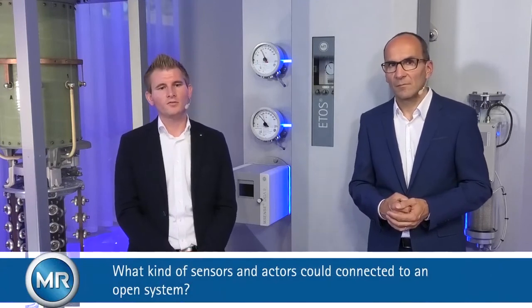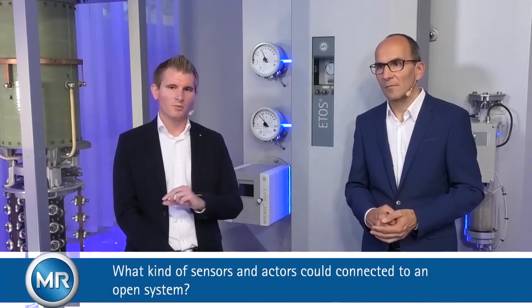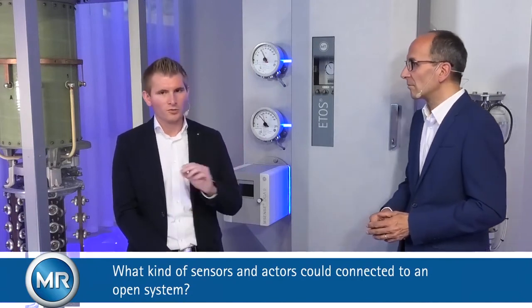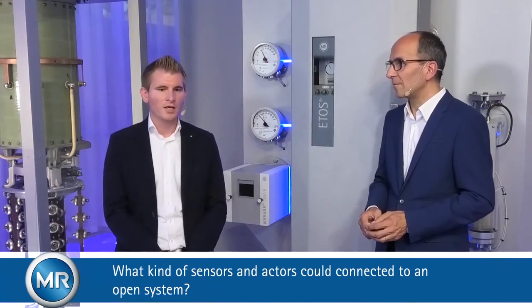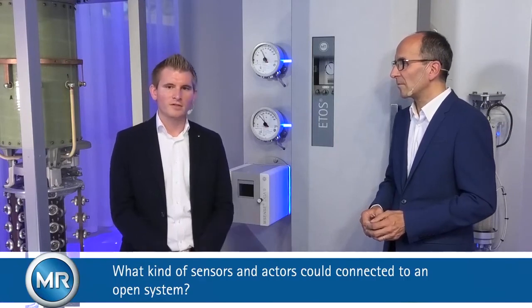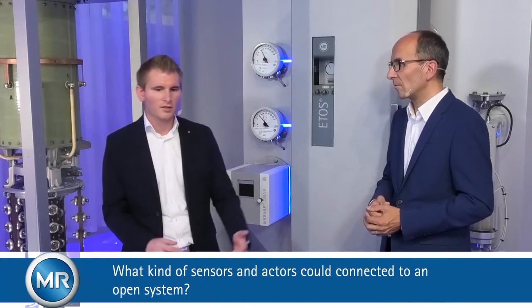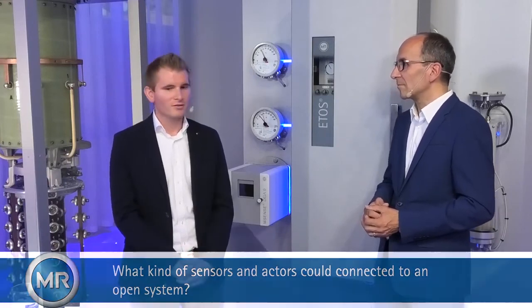And besides all of that, if it's not a common sensor from the energy world, but you would like to add something for the weather, we have the common standard SI units, over 80 SI units prepared in the software. You only choose what the incoming signal is, let's say 4 to 20 milliampere or 0 to 10 volts. And then you choose the common SI units like pressure, Kelvin, and so on.